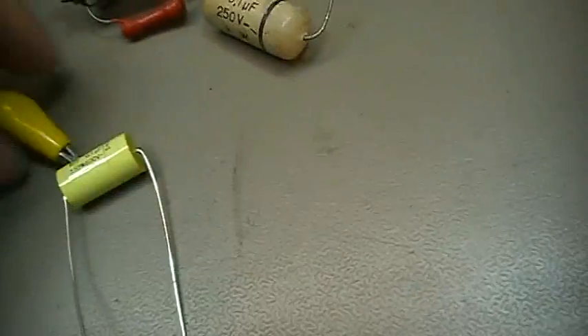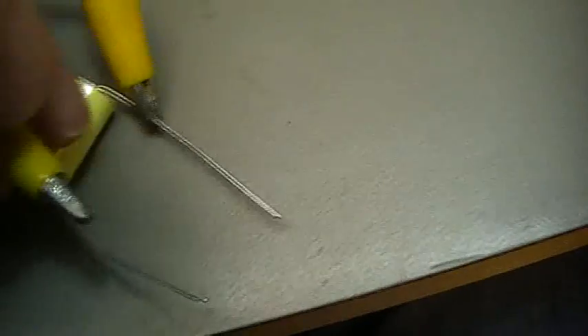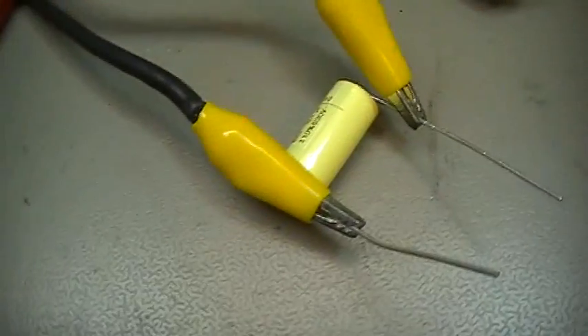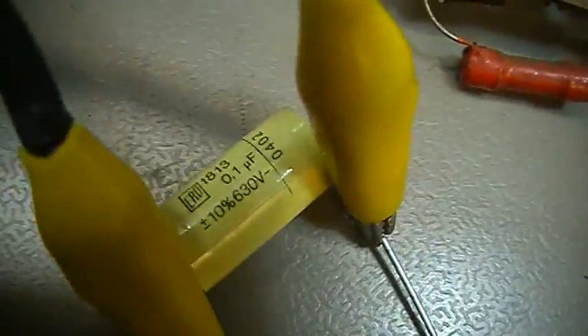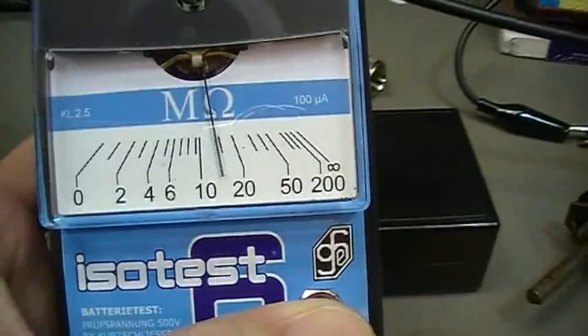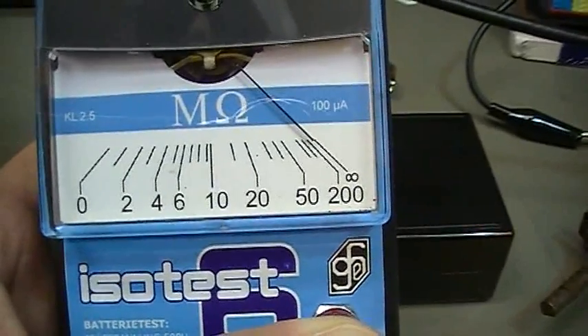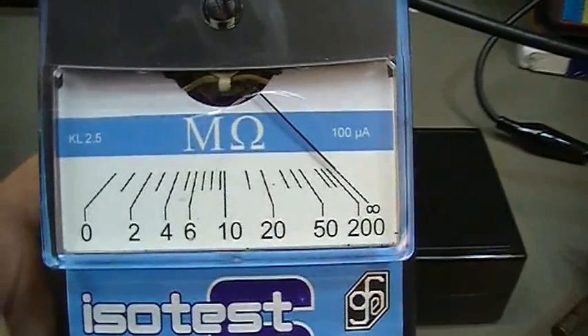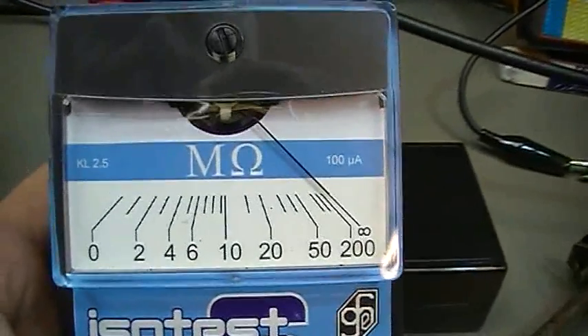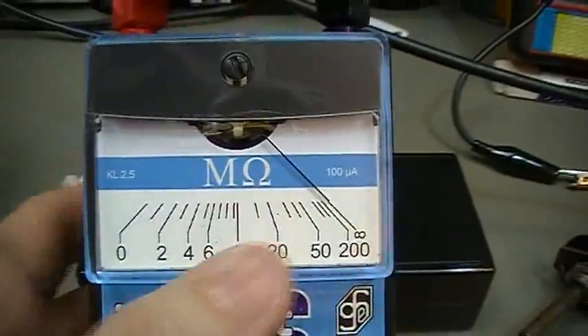Let's check the same with this axial capacitor. We connect it to the isolation tester, and as we know from the label, it's also good for 630 volt, so I can leave it on 500 volt. I push the button - same behavior, it moves back to infinity after charging, which means there's no current flowing, and it's completely blocking the DC voltage.